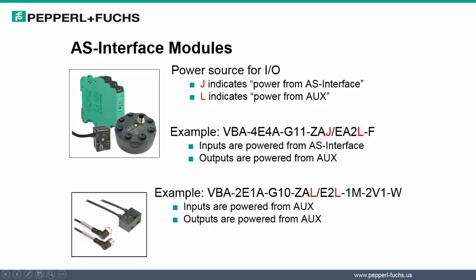Let's now take a closer look at power source requirements for AS Interface modules. Model descriptions are very helpful in determining the power supply requirements. From the J and the L noted in the description, we can determine where the power is needed. In the first example on the slide, we have a G11 module. In the model number description, we have a J and an L noted, indicating that the module has power requirements both from AS Interface, yellow cable, and aux black cable.